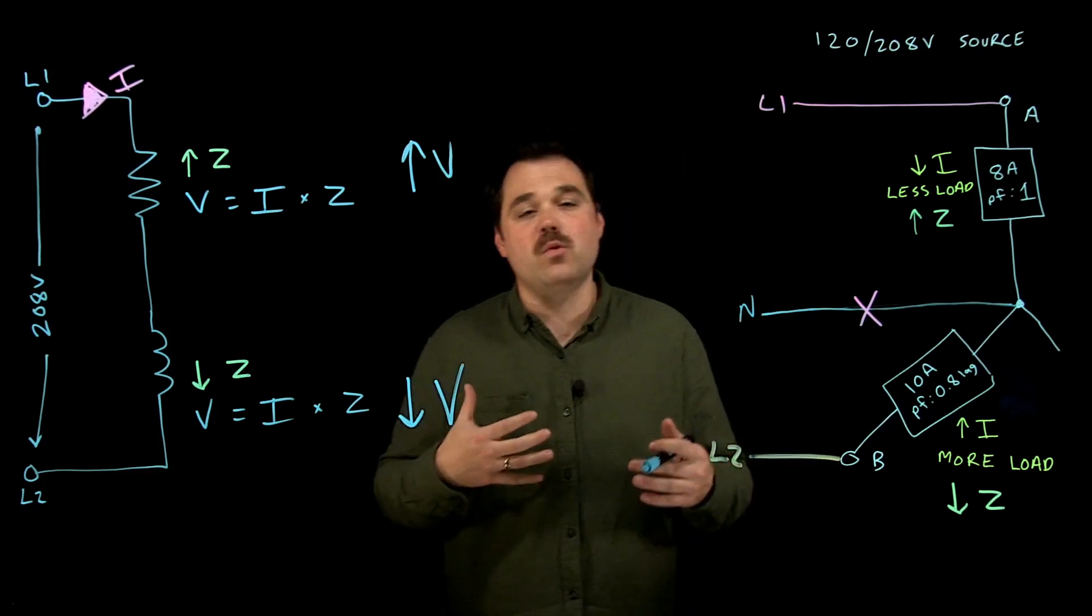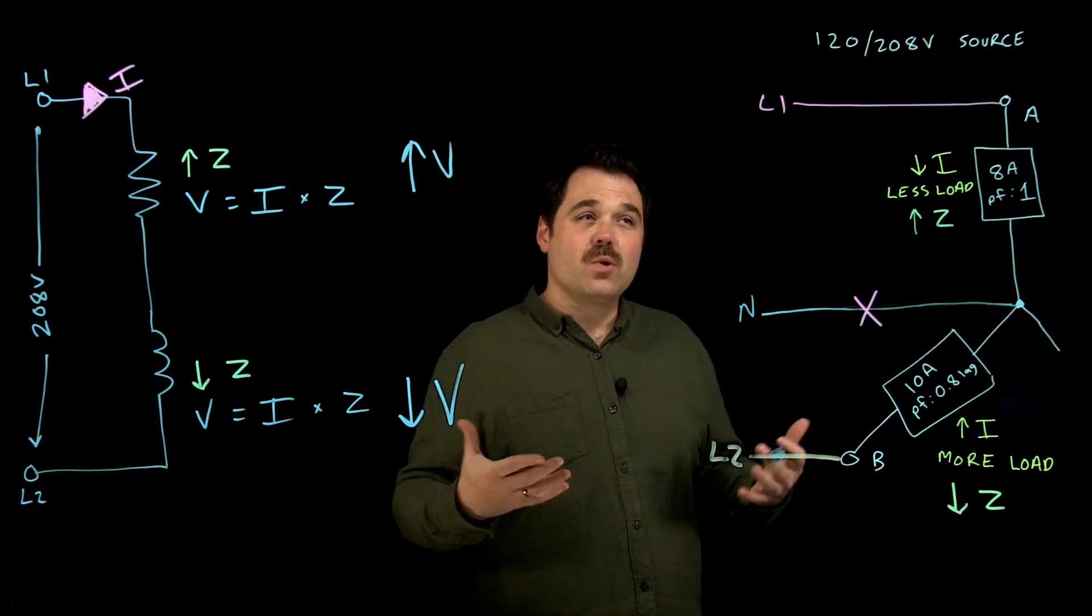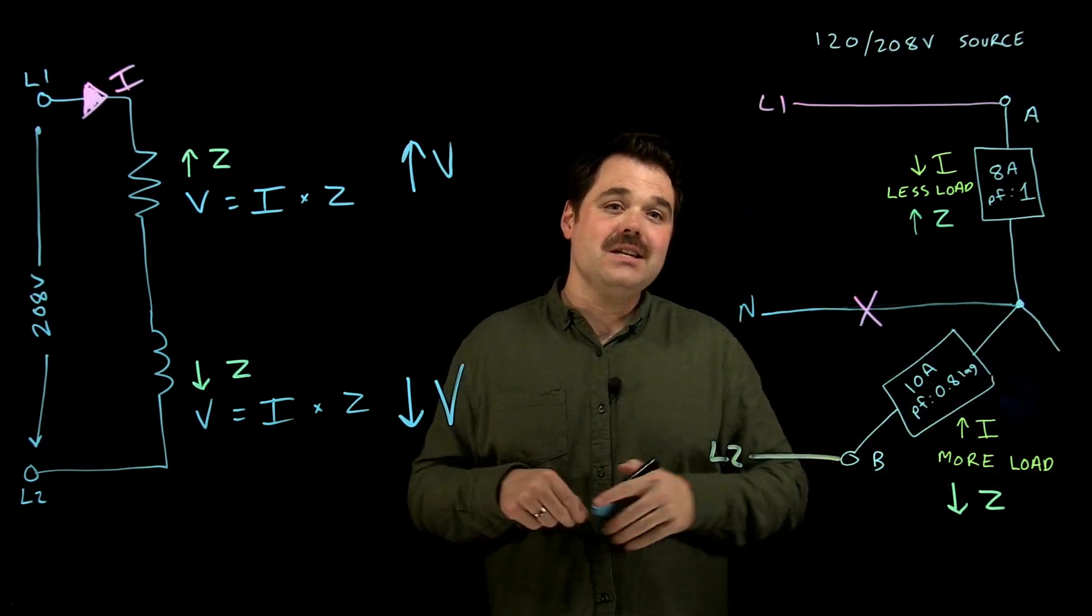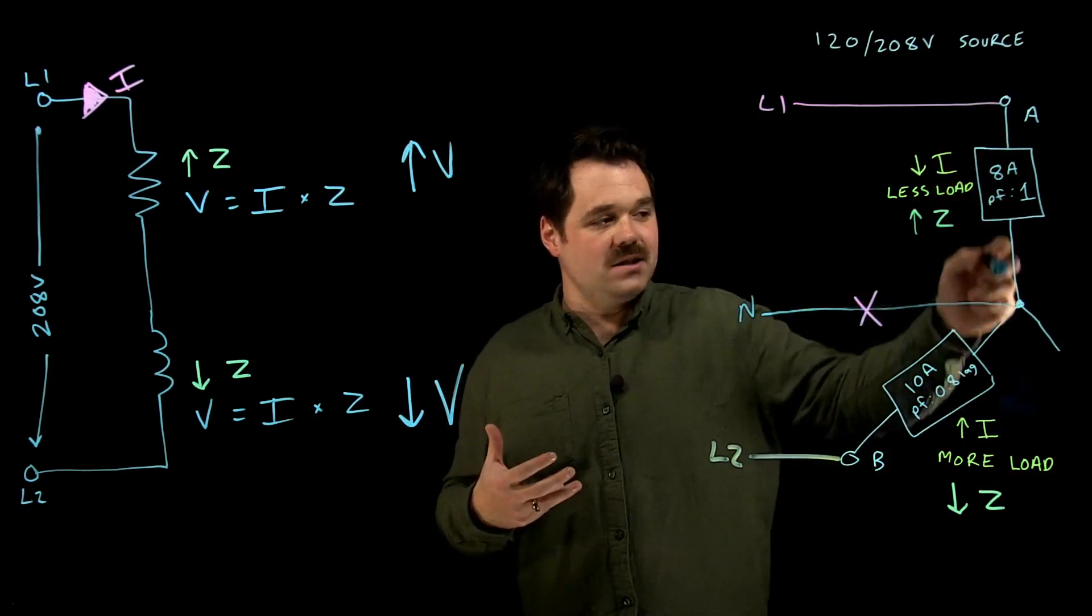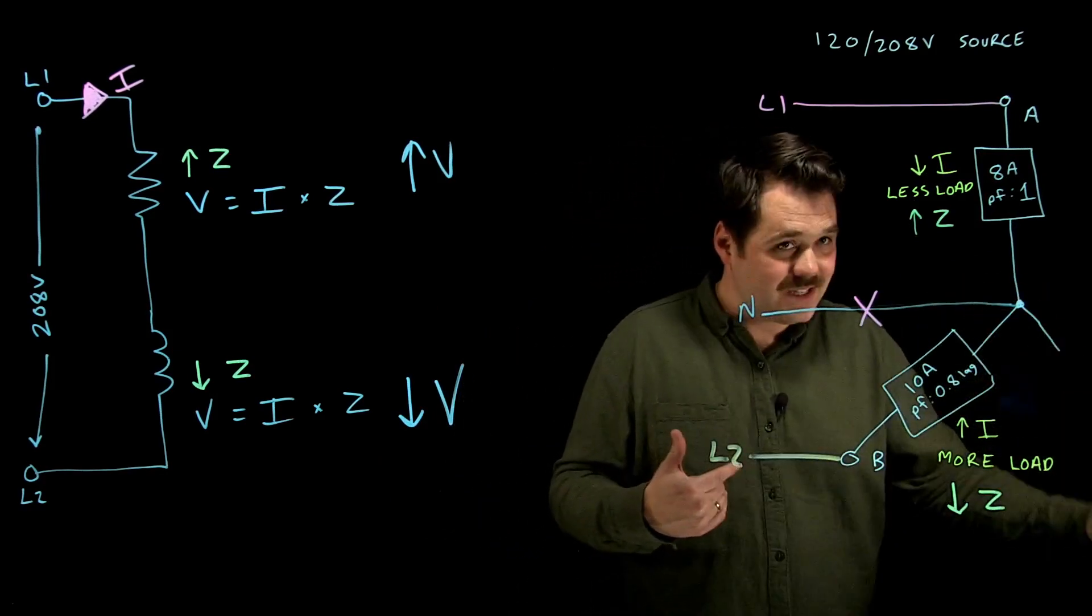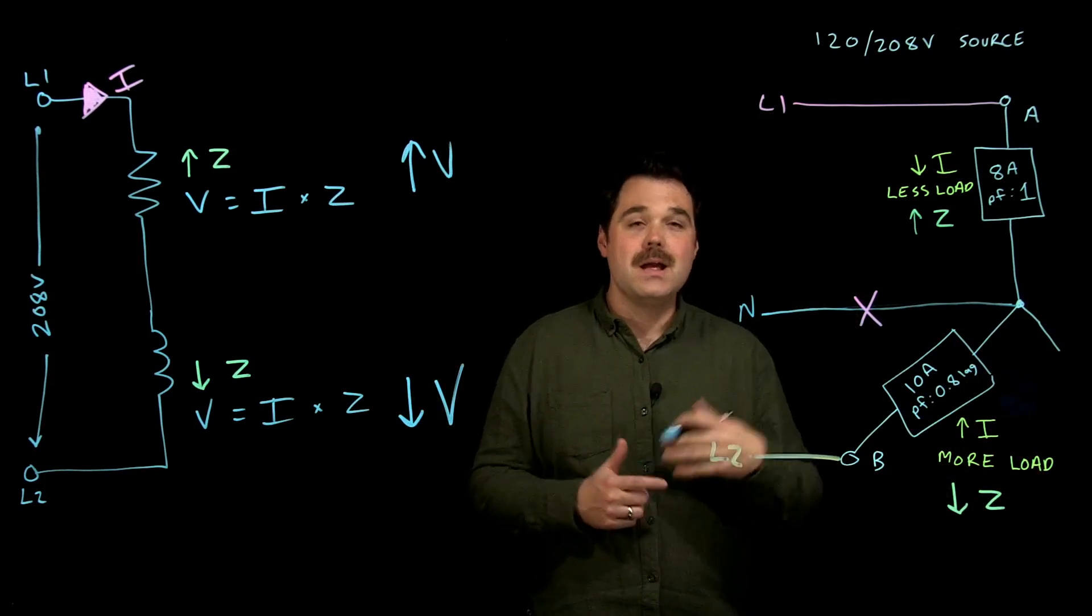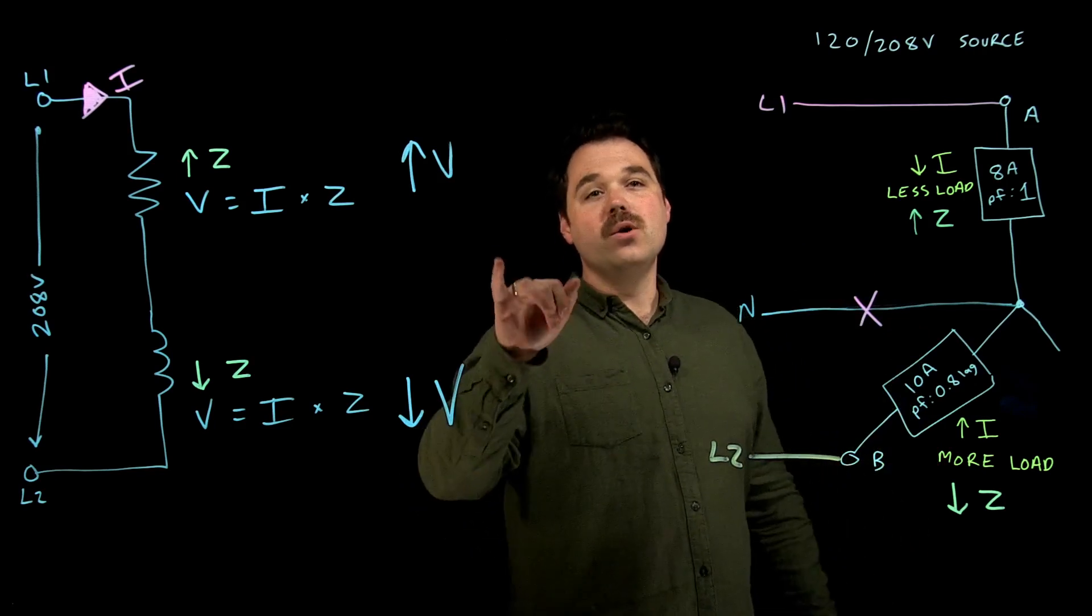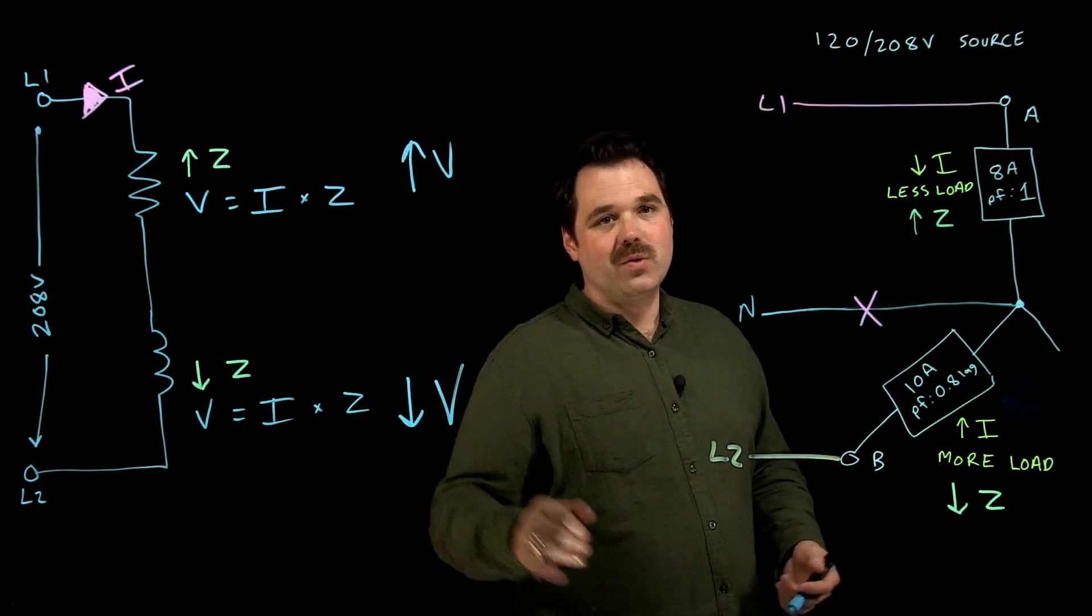So I do hope that clears up some questions about what happens when we do see a neutral conductor break. Of course, in this example talking about a three-phase source, we didn't discuss anything on phase C, but the same rules would apply. You would have phase A and phase C in series with 208, you would have phase B and phase C in series between line two and line three. But those general rules still apply: higher impedance load, higher voltage drop; lower impedance load, lower voltage drop.